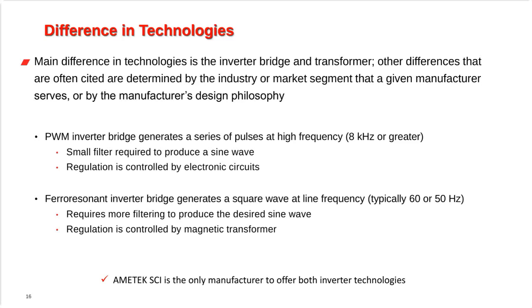But in general, a PWM inverter bridge generates a series of pulses at a high frequency, and it can be 8 kilohertz or greater. And therefore, you need a smaller filter to produce a sine wave. And also the regulation is controlled by electronic circuits. So there is much more processing power going on inside a PWM system. There's a lot more control, there's a lot more switching going on inside the PWM. For a ferro-resonant inverter bridge, it just generates a square wave at the line frequency. In the US, that's 60 hertz. In Europe and elsewhere, it can be 50 hertz. It does require more filtering to produce the desired sine wave. And the regulation is controlled by the transformer.